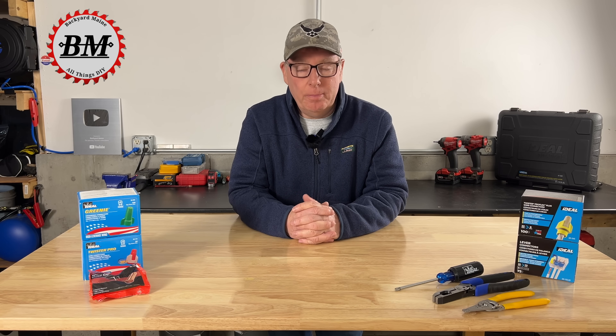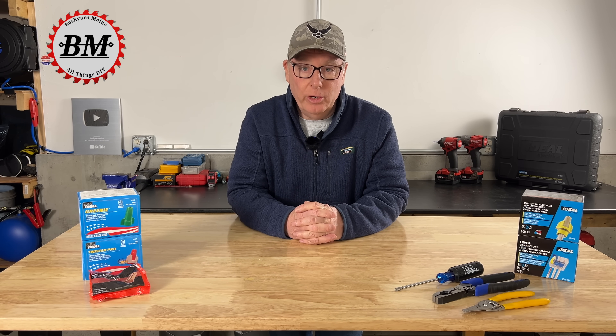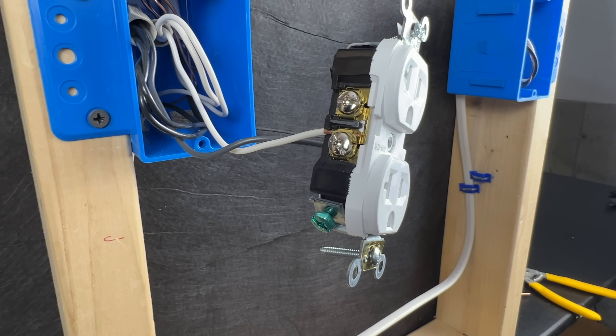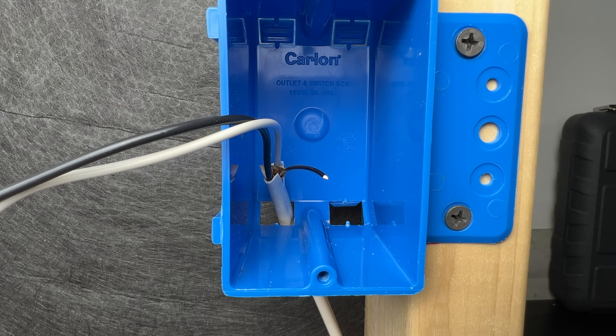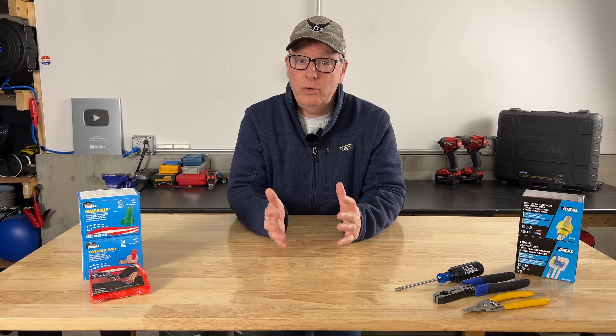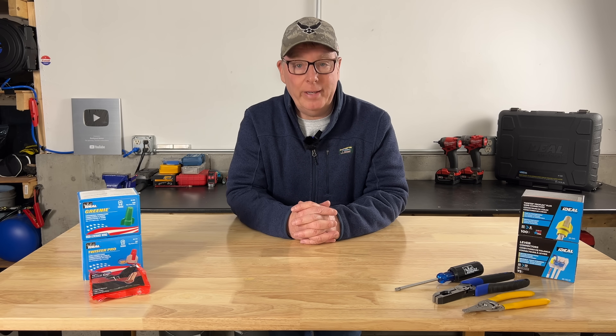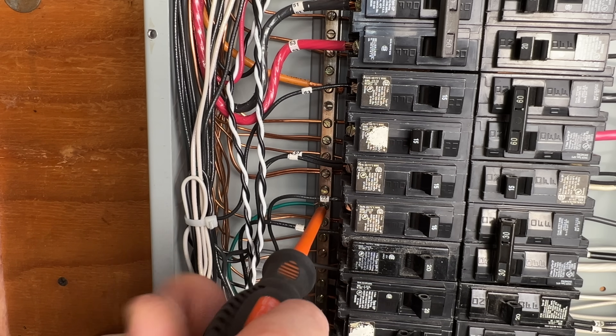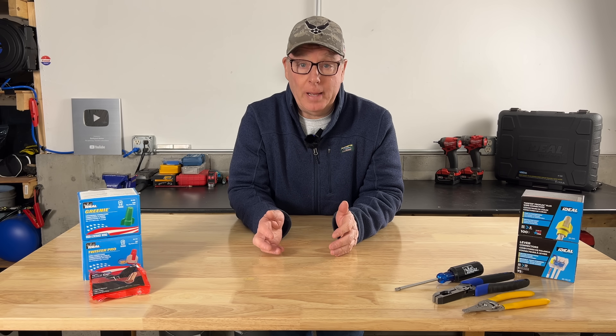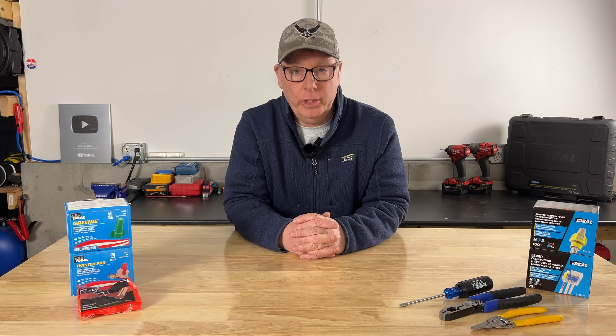Hey guys, John here with Backyard Maine. I've been an electrician for over 40 years and I've seen ground wires that were connected poorly, not connected at all, or even cut off completely. The circuit will still function without them, so these issues often go undetected and they can actually be quite dangerous. Without a ground path back to the grounded conductor, fault current can take an alternate path which could create a fire, shock, or an electrocution hazard.